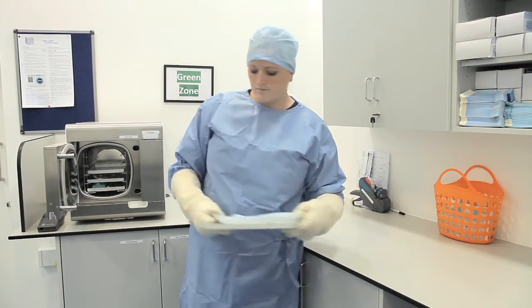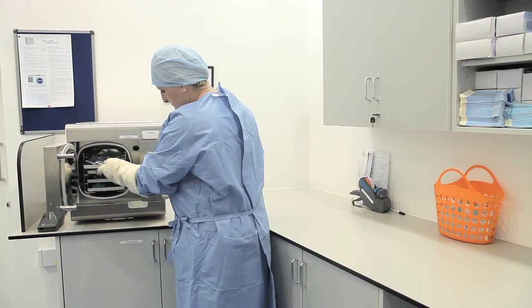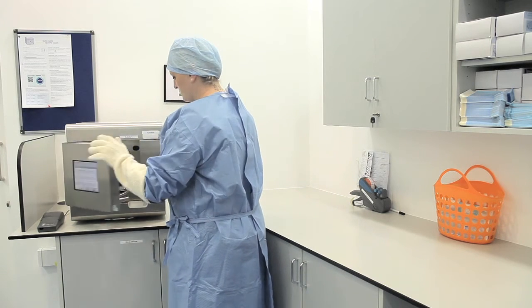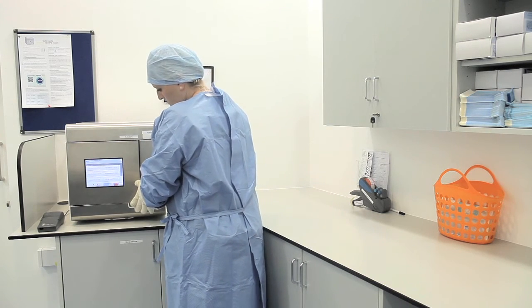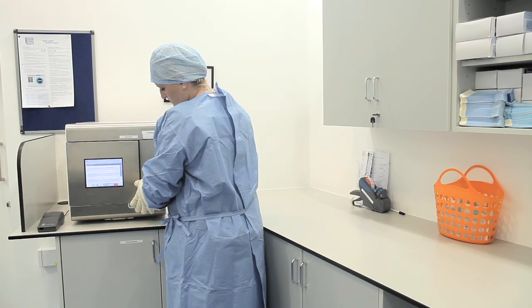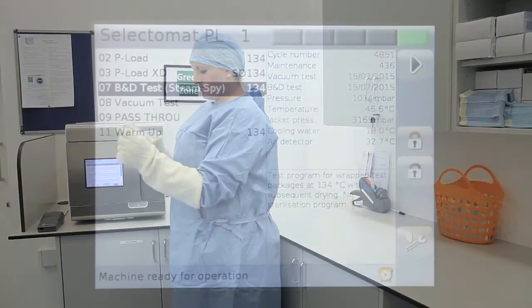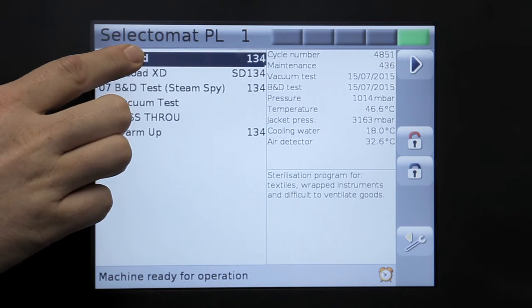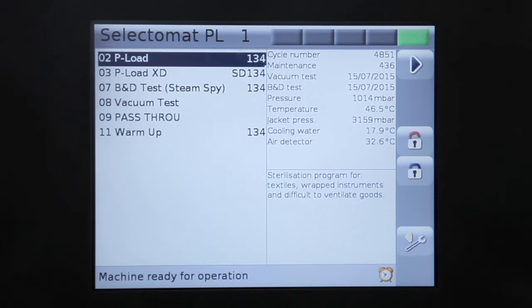After loading the autoclave with the labelled RIMD, the dental healthcare worker selects the appropriate cycle for sterilisation, which is 134 degrees centigrade for 3 to 4 minutes. This is the recommended temperature that must be reached in order for sterilisation to be successful.